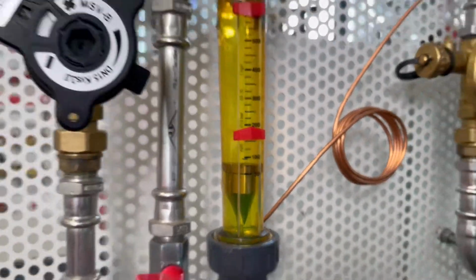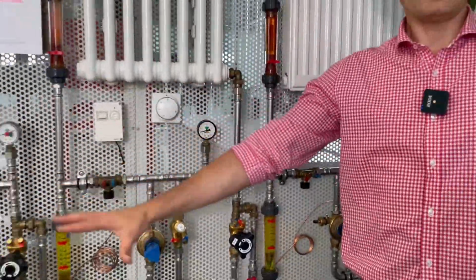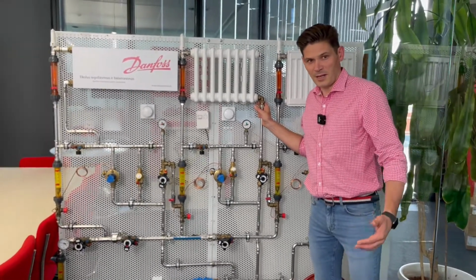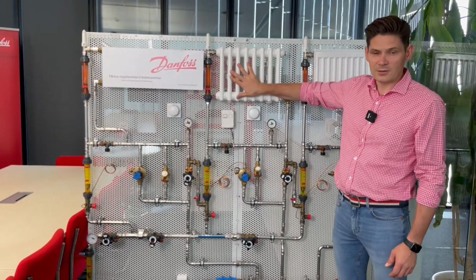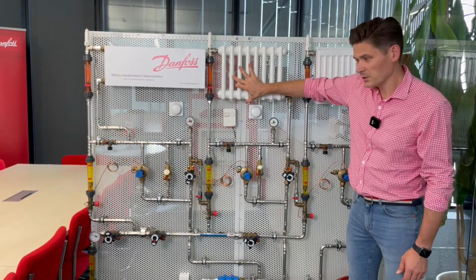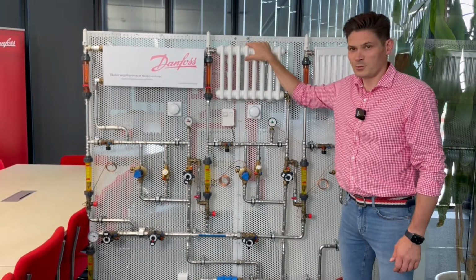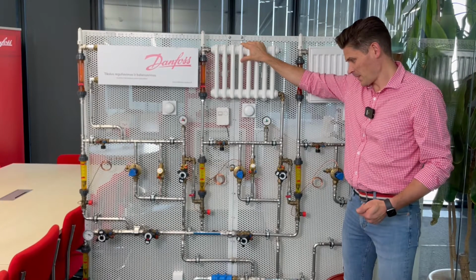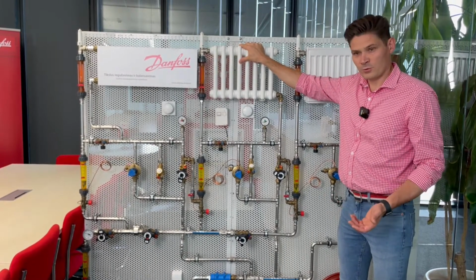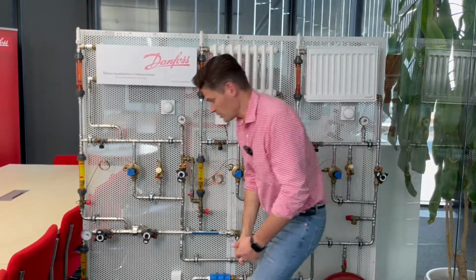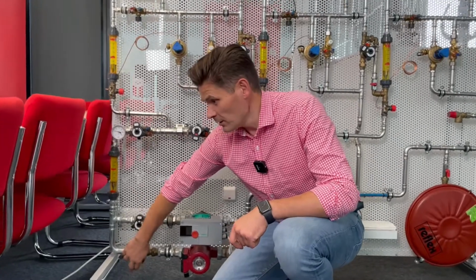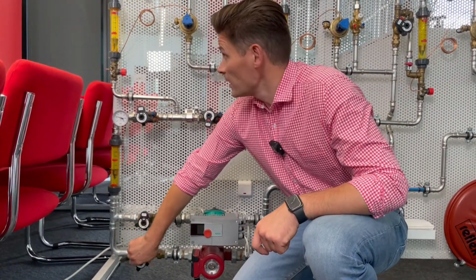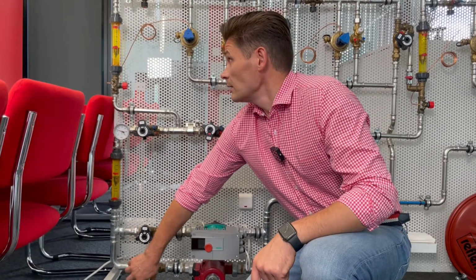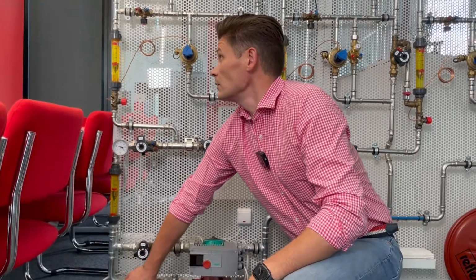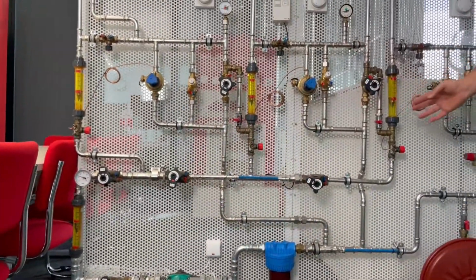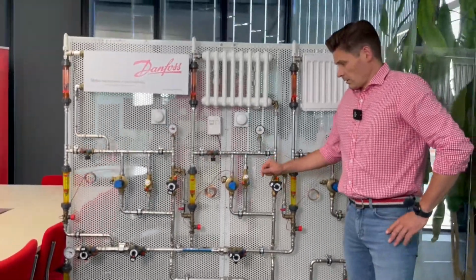So now every tenant is calling the maintenance company and asking questions. Why are our radiators cold? And what are you doing with our system? It is either heating too much or heating too little. And there is nothing much to do other than for the maintenance company to come again and increase the pump head to fulfill the needed requirement. So I just open this manual balancing valve and set the same flow as it was, 200 liters for each riser.